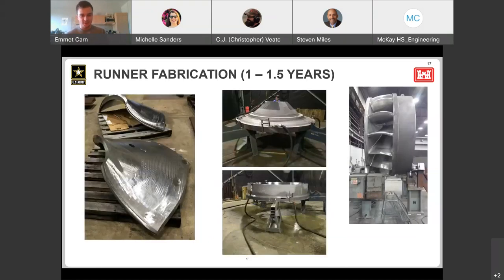Here are some pictures of fabrication of a turbine runner. A runner is just what you think of when you think of a turbine—the blades that cause the rotation. We actually travel to the foundries to witness these runners being manufactured, and we do a lot of material testing on the steel used. We'll cut off parts of the steel that was cast and test it to make sure those material properties are what we want and require.